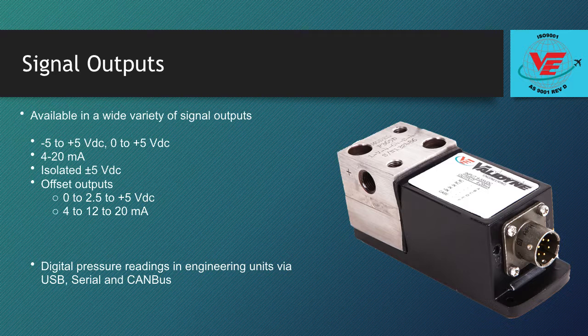Voltage outputs are also available with isolation from the power supply. The P365 can be ordered with 4 to 20 mA outputs over 0 to plus full-scale pressure, and this is similarly available in an offset version where 4 mA equals minus full-scale pressure, 12 mA equals 0 pressure, and 20 mA equals plus full-scale pressure. The P365 will operate from any DC power source between 9 and plus 55 volts DC.